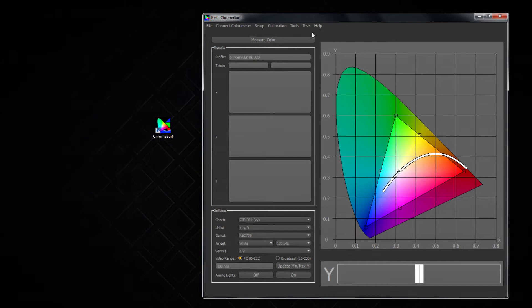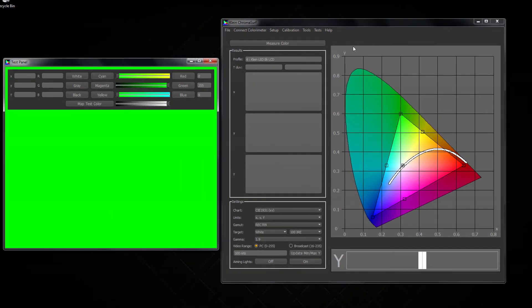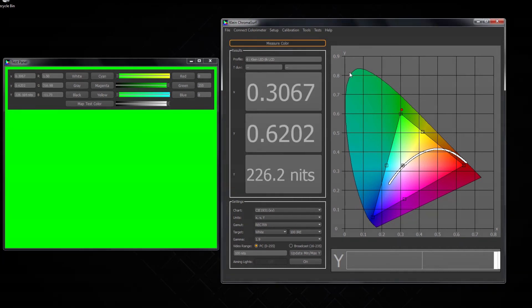Now we can get our first measurement. Go to tools and open the test panel. This is the area of the screen we will measure. Make sure the K10A is pointed only at this panel. Now if we hit measure color, we get our xyY values.